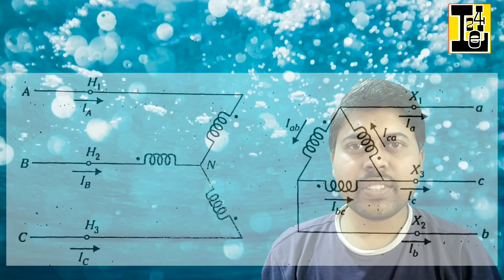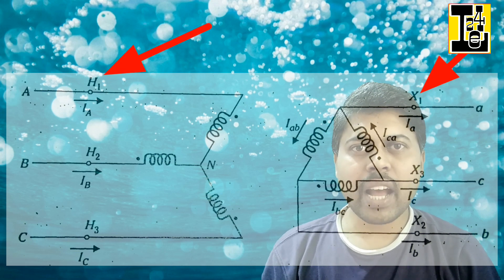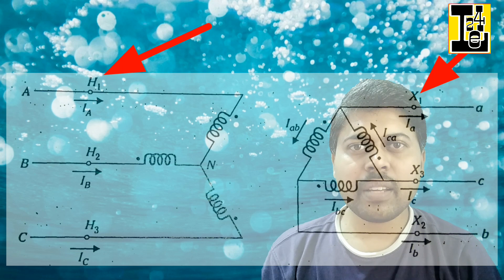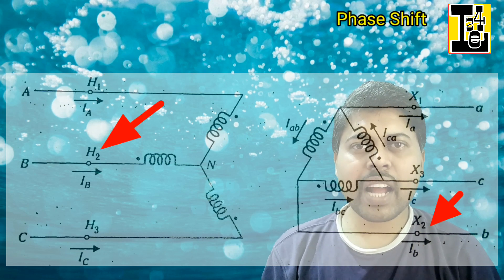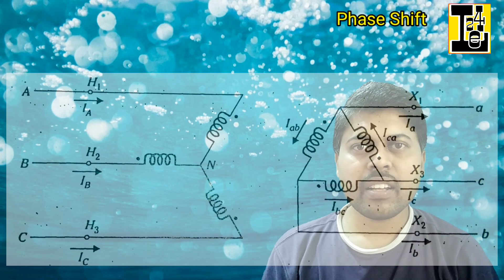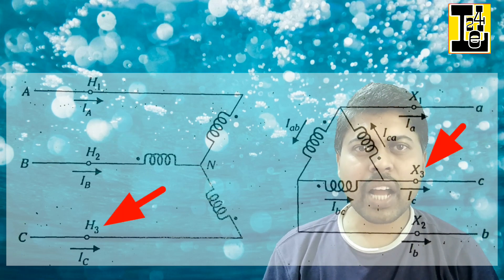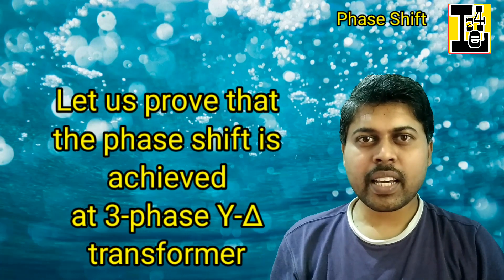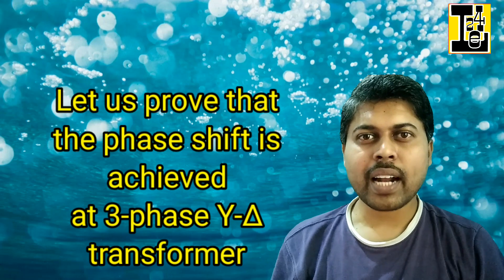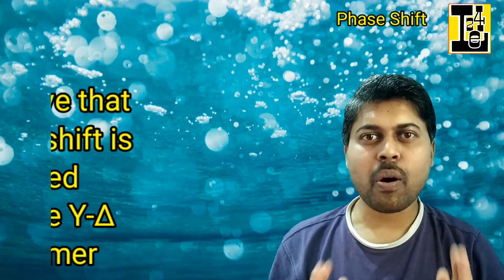According to the ANSI standards for designating the terminals, the voltage at H1 will lead the voltage at X1 by 30 degrees. Similarly, the voltage at H2 will lead the voltage at X2 by 30 degrees, and the voltage at H3 will lead the voltage at X3 by 30 degrees. Let us go through the phasor diagrams which will prove that the phase shift is achieved in a star-delta transformer.